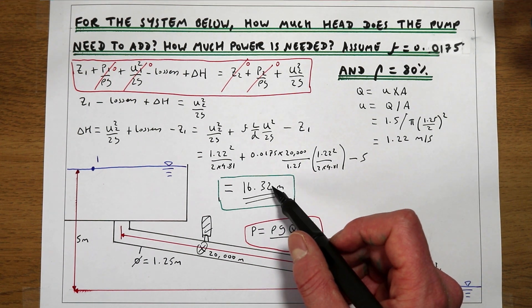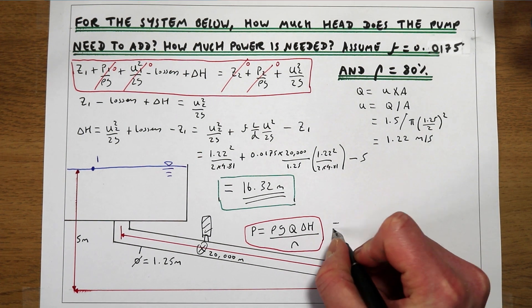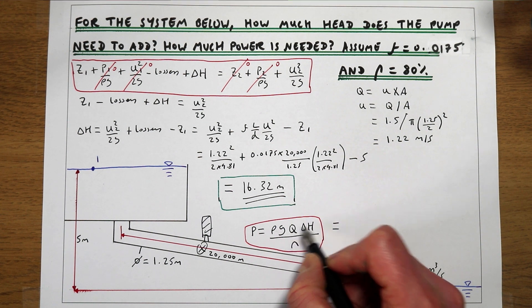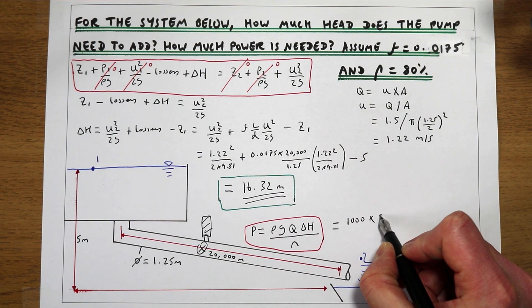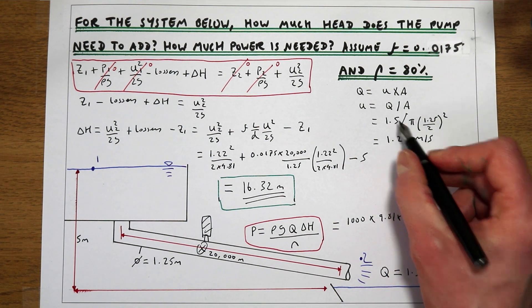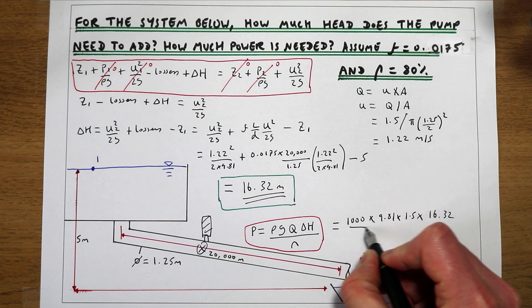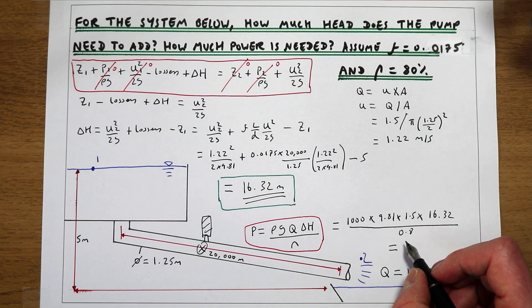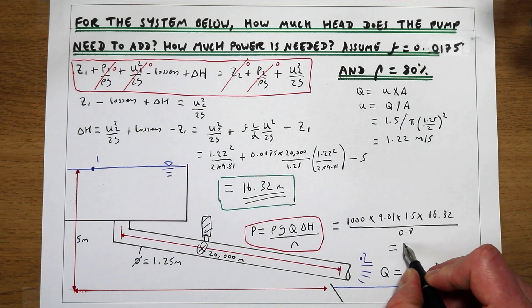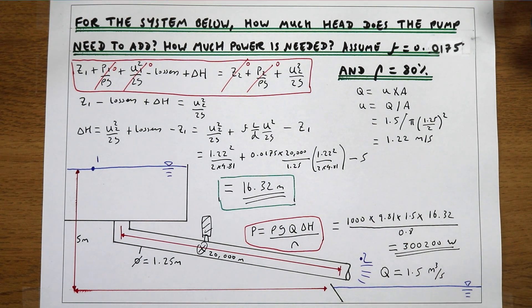Now we have that figure, we can work out how much power we need to provide to the pump. Power equals density of water times gravity times flow rate times pump head, divided by pump efficiency. With density of water, g, flow rate of 1.5 m³/s, head of 16.32 m, divided by efficiency of 0.8 (80%), this tells us that the power the pump needs to provide is approximately 300,200 watts — so about 300 kilowatts.